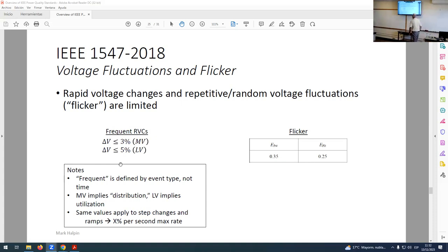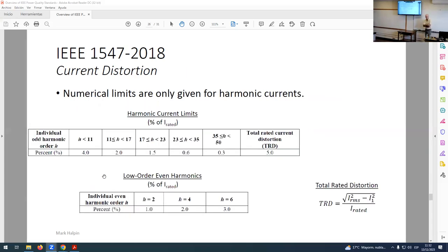In addition to these instantaneous or step change limits, we also have the same numbers defined as far as ramp rates are concerned. These same percentages cannot be exceeded in terms of ramp rate, as a percentage change per second. Harmonics: in 1547 we only give limits for the harmonic current emissions. These are the individual harmonic limits. Two things about this are interesting. One thing is this row is the most restrictive row of all of the rows in 519. This is the most restrictive.